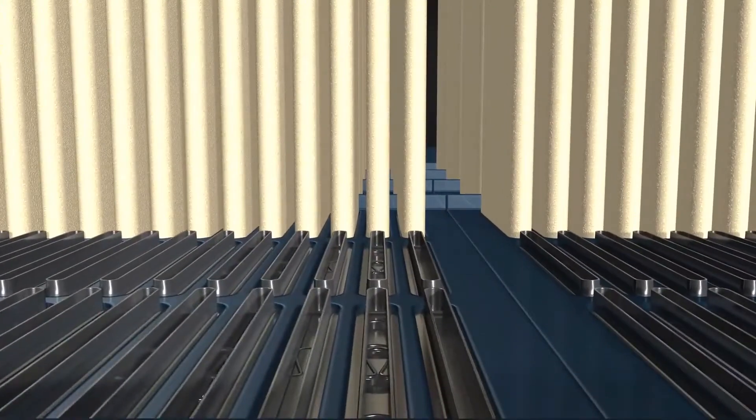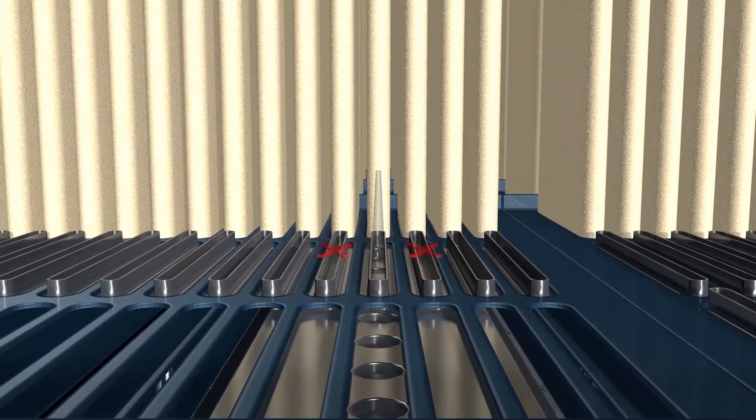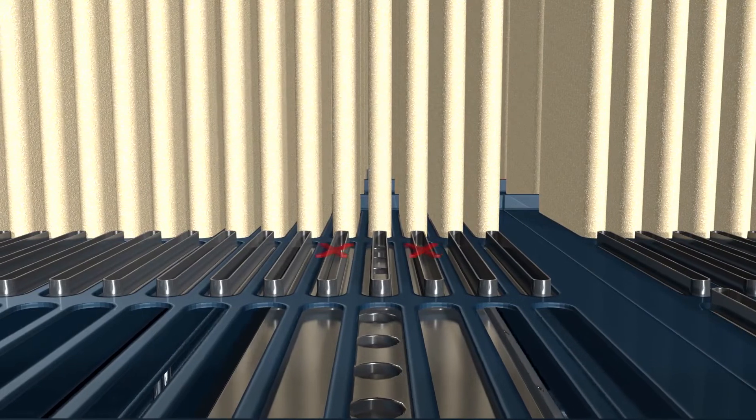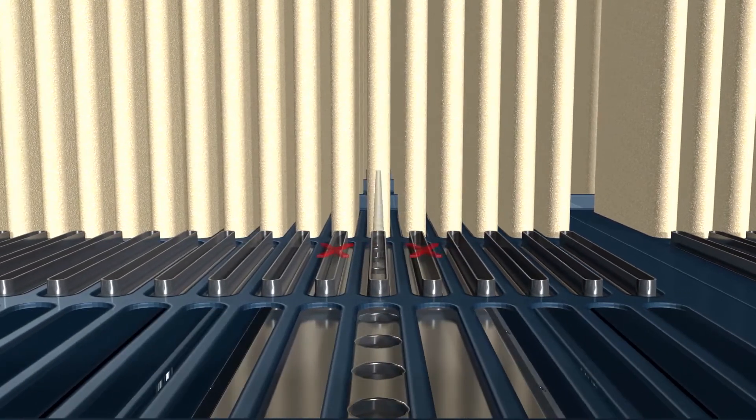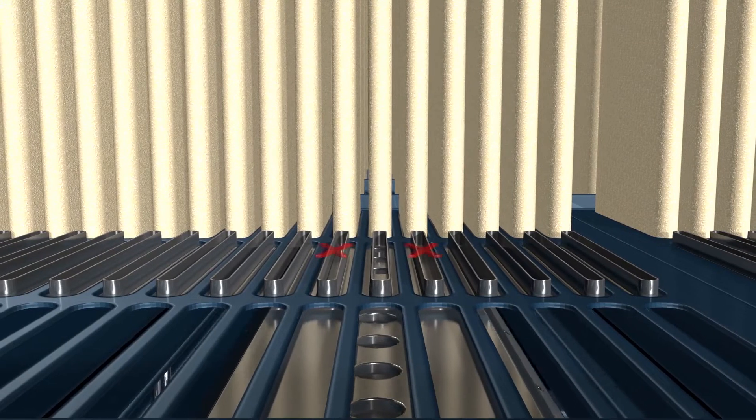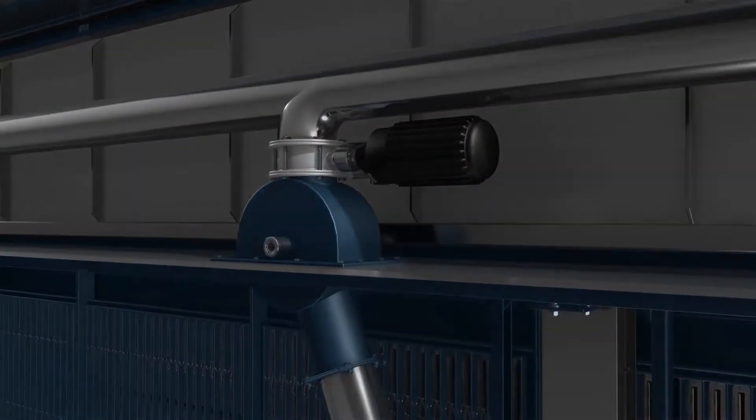The cleaning carriage moves from one filter row to the next, initiating the cleaning cycle on each row. The detached dust cake is prevented from caking on neighbouring filter bag rows during the cleaning process, as the adjacent filter bag rows are offline during the cleaning process.